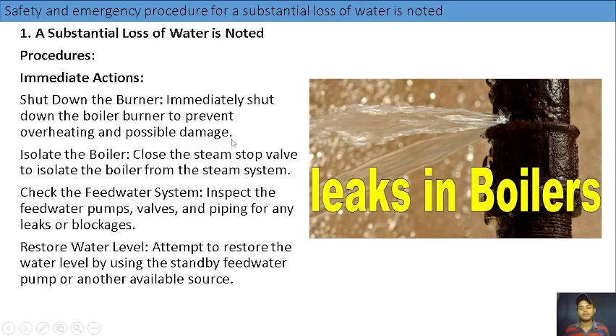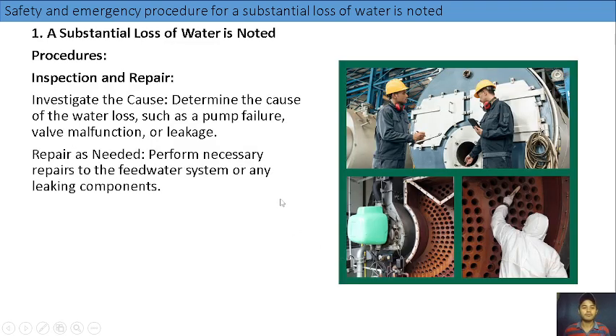So, procedures, immediate actions. Shut down the boiler burner immediately to prevent overheating and possible damage. Isolate the boiler: close the steam stop valve to isolate the boiler from the steam system. Check the feed water system: inspect the feed water pumps, valves, and piping for any blockages or leaks. Restore water level: if everything is now okay, attempt to restore the water level by using the standby feed water pump or another available source.